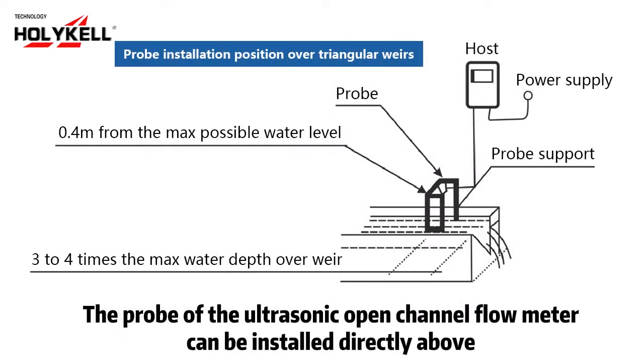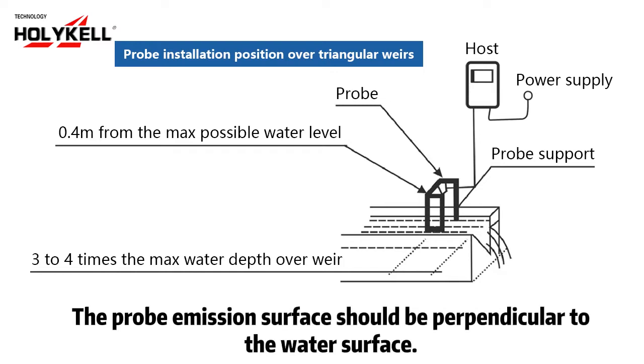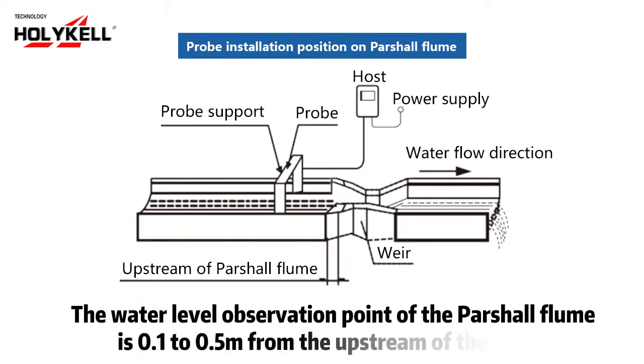The probe of the ultrasonic open channel flow meter can be installed directly above the water level observation point of the weir. The probe emission surface should be perpendicular to the water surface. A spirit level can be placed on the probe cover to ensure the probe is aimed at the water surface. The water level observation point of the Parshall flume is 0.1 to 0.5 meters from the upstream of the flume.